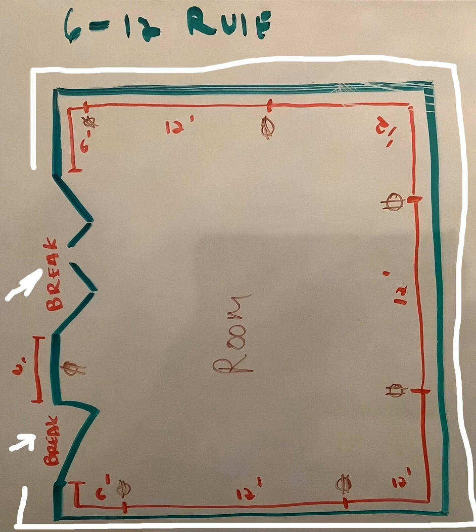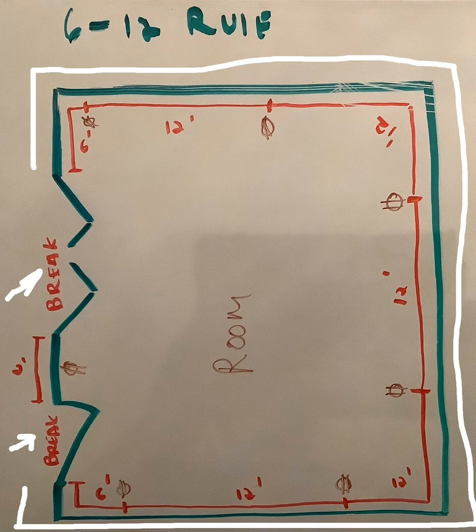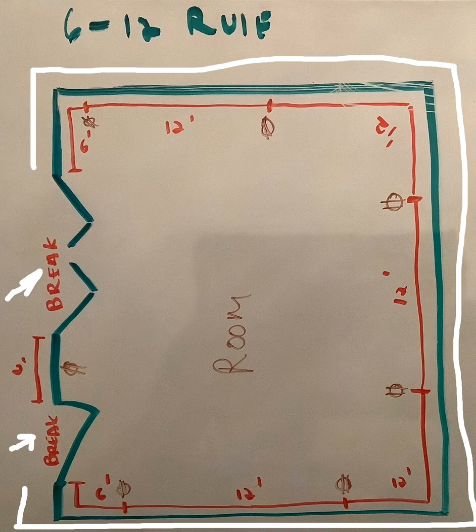The code says, receptacles shall be installed such that no point measured horizontally along the floor line of any wall is more than six foot from an outlet. What does that mean?